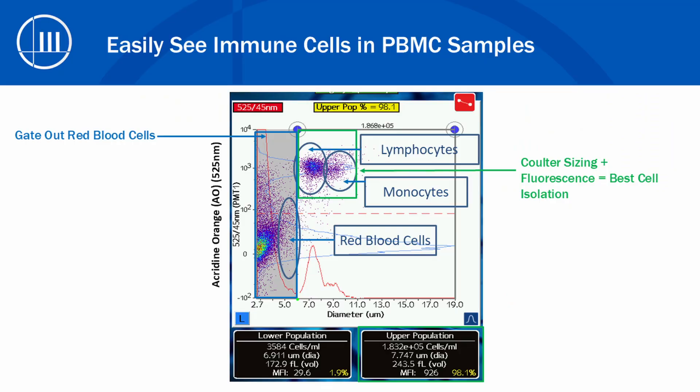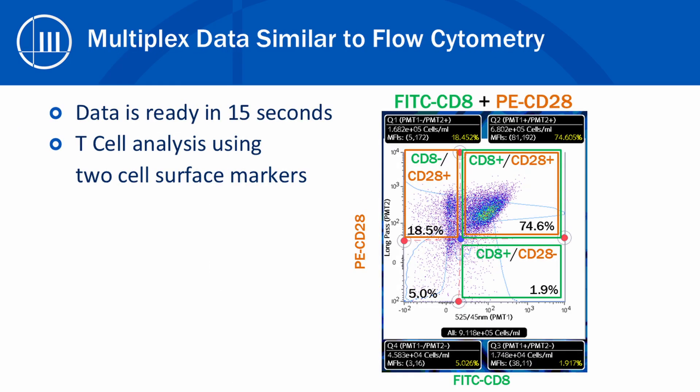That many data points results in incredibly reproducible data, with a coefficient of variation often below 5%. You're also able to very easily differentiate different cell types, as can be seen from this PBMC sample data. A full sample measurement only takes 15 seconds, even for runs with multiplex fluorescent data, like this T cell sample with two CD markers.